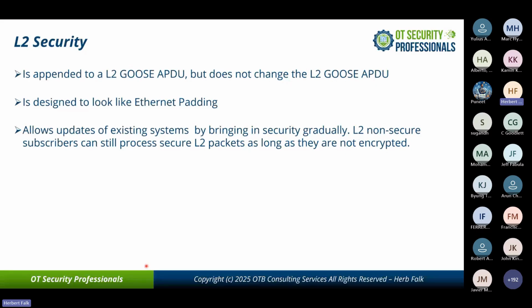The layer 2 security was designed to allow migration of layer 2 GOOSE systems. Because it's appended to the end of the layer 2 GOOSE APDU but does not change the layer 2 GOOSE APDU, it looks like Ethernet padding. This allows existing systems to bring in layer 2 security and have it ignored by non-secure layer 2 subscribers.